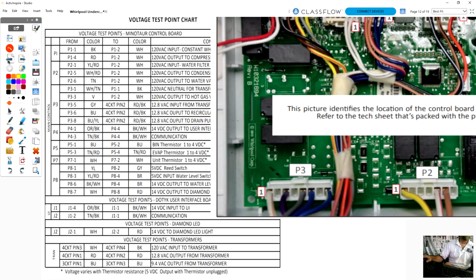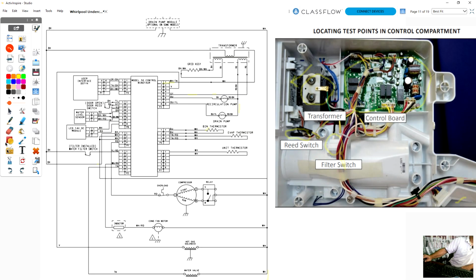Going back to the control board here, let's go to the diagram first. So we have several different voltages going on. Here's our circulation pump, here's our drain pump, bin thermistor, evap thermistor. The unit thermistor is the one I showed you that's on the bottom by the induction coil. You have the user interface. This is the front with the LED lights that you're pressing to activate.